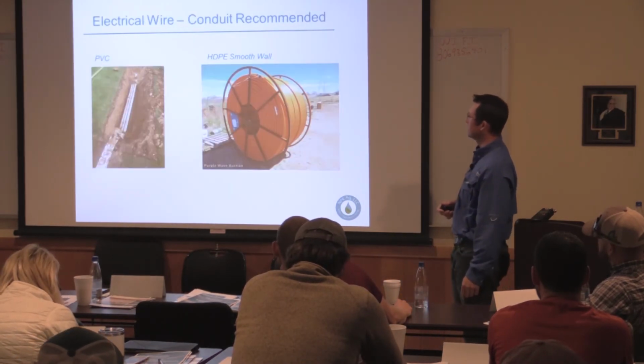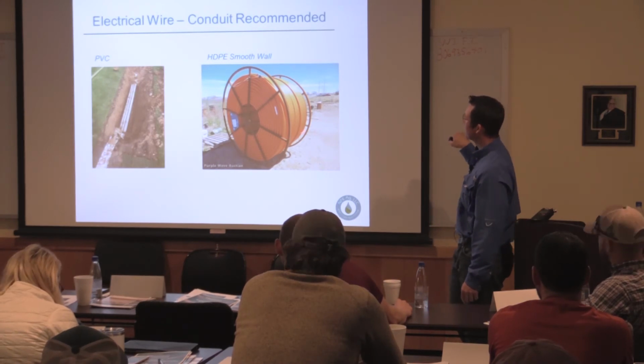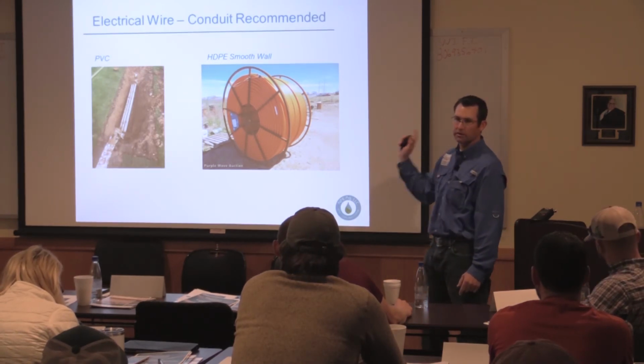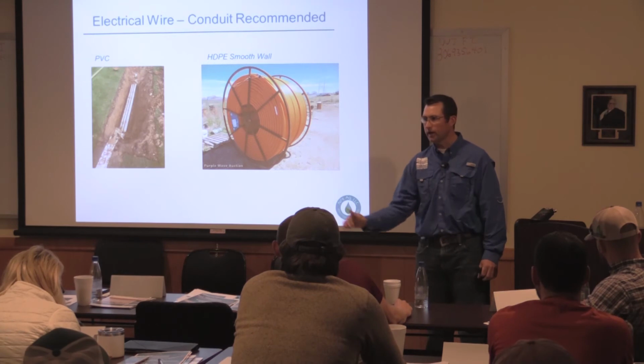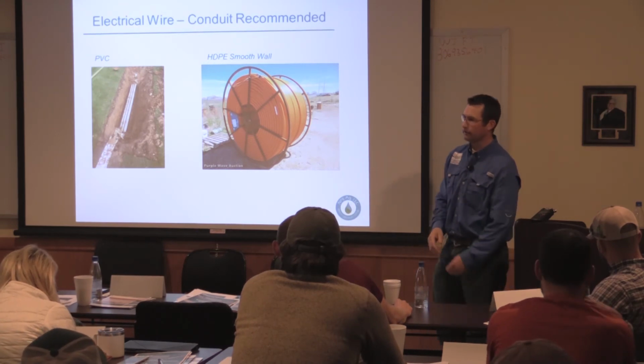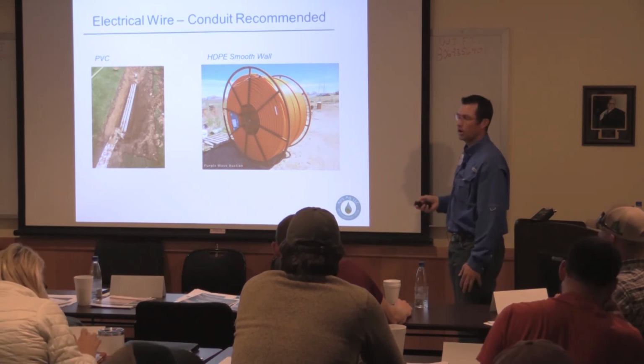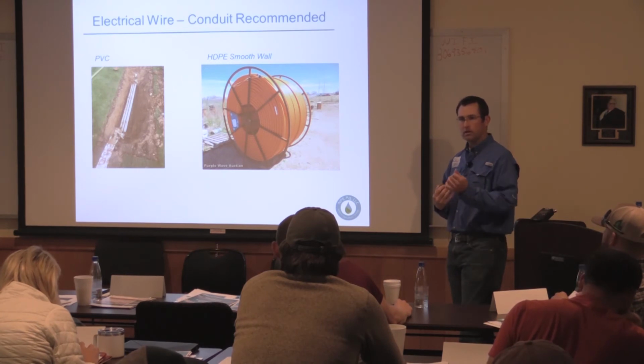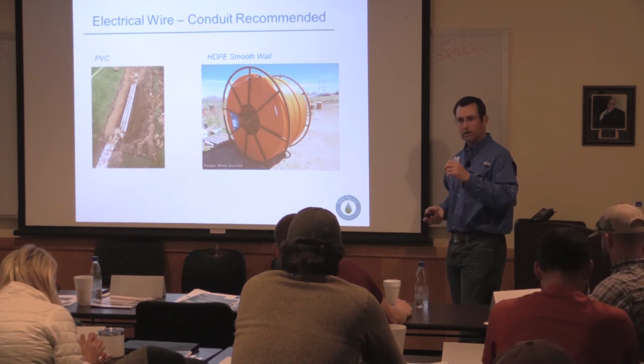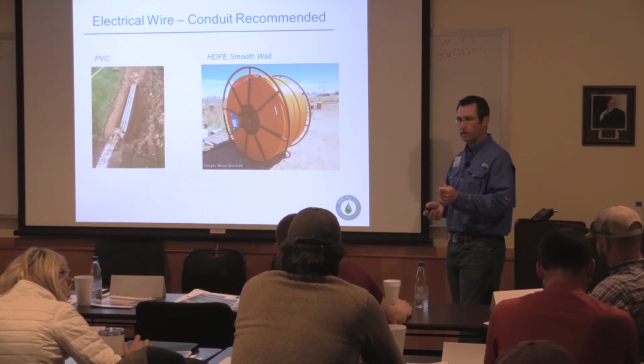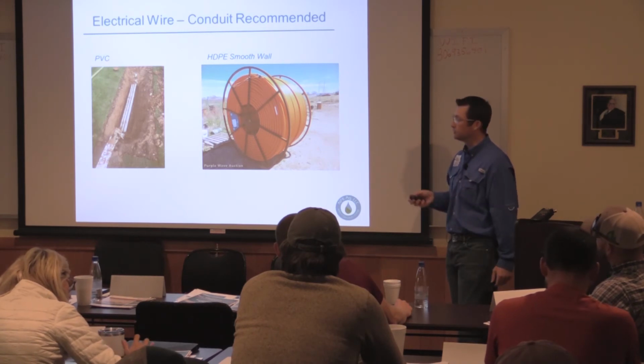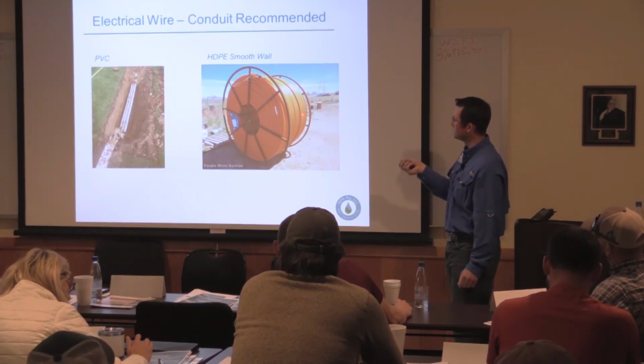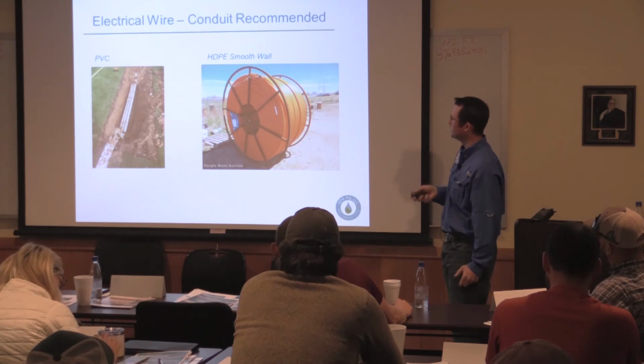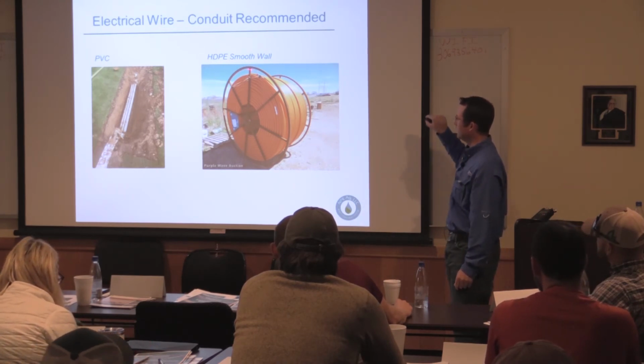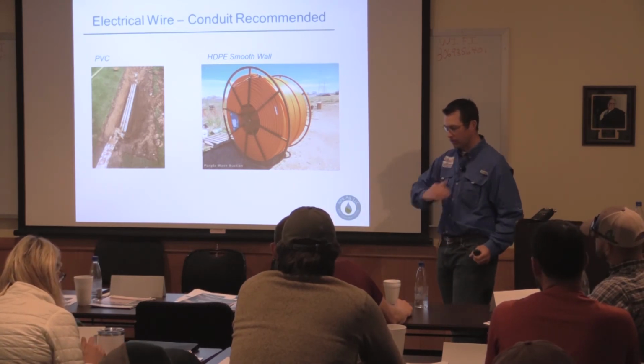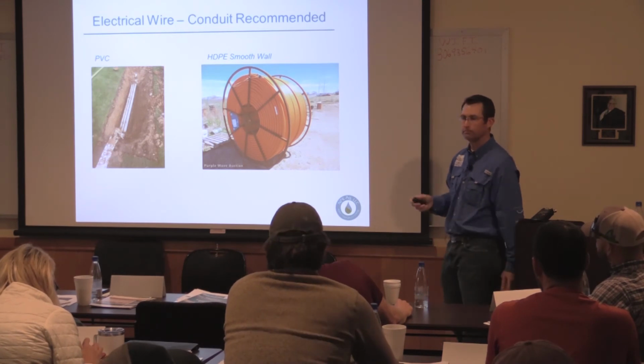A couple of pictures to look at. Conduit is recommended on all of this. I know throughout the country here, there's a lot of direct burial line just put in. I have not seen direct burial line last very long. In my experience, the interaction with the coating, the aluminum in it, and the soil, it just degrades. So you're going to want to invest in a little bit of conduit. This is a nice smooth wall HDPE. You can have your wire sink in that, and so you just drop it in the hole as you go. That's what I recommend doing.